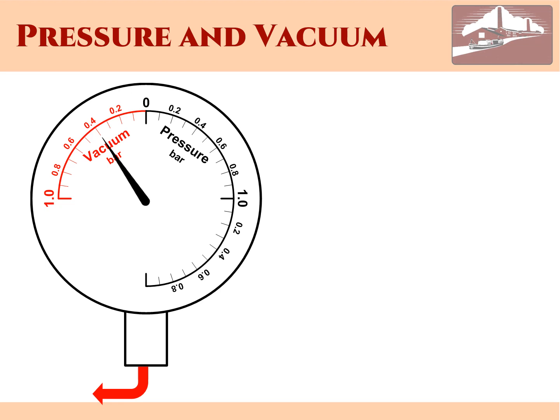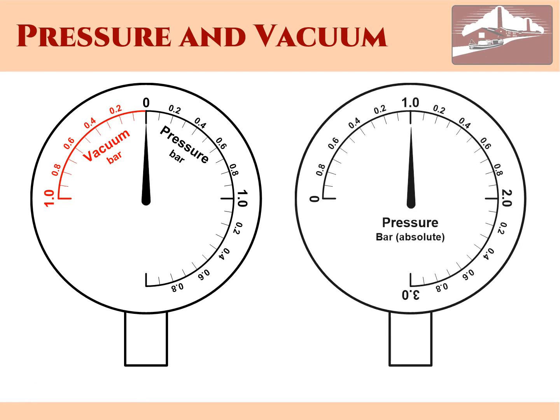If absolutely all the air is removed from our vessel, the pressure inside will be 0, and the gauge will now show -1 bar or 1 bar vacuum. Why not simply move the scale on the gauge to show 0 at this point? This is known as 0 bar absolute, or 0 bar A for short. Normal atmospheric pressure is 1 bar A, and what we normally think of as vacuum is any pressure between 0 and 1 bar. In the following description of the evaporation process, absolute pressures are used throughout.